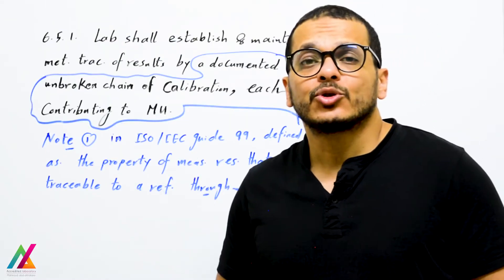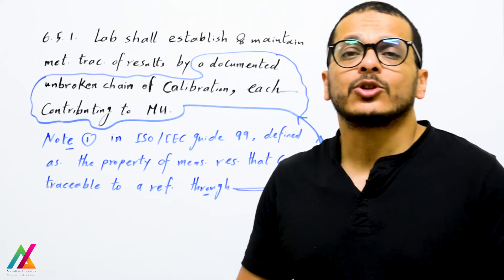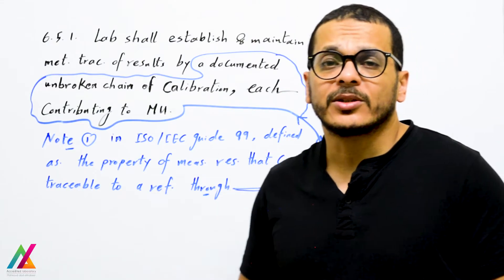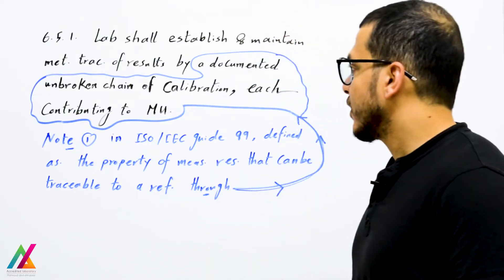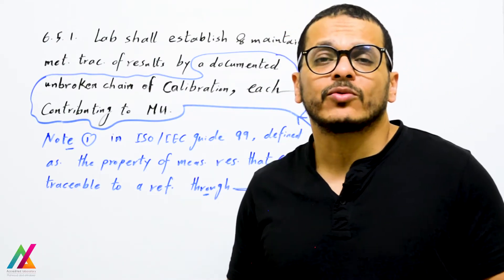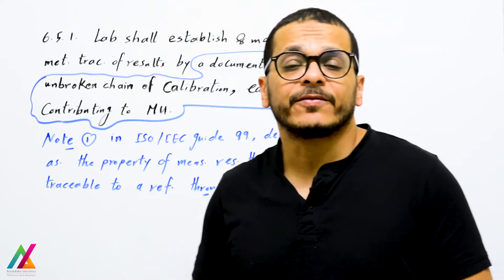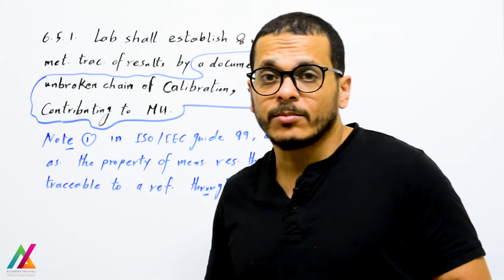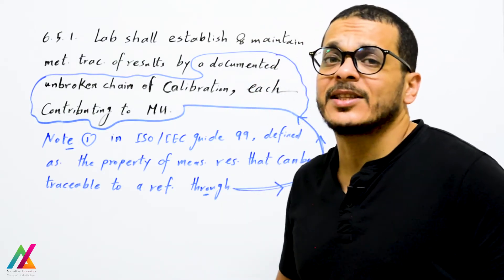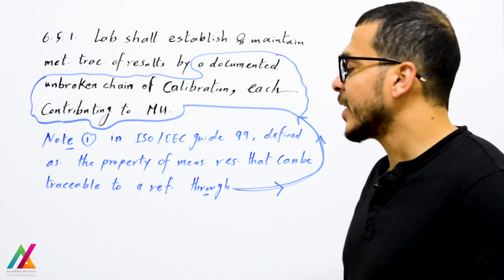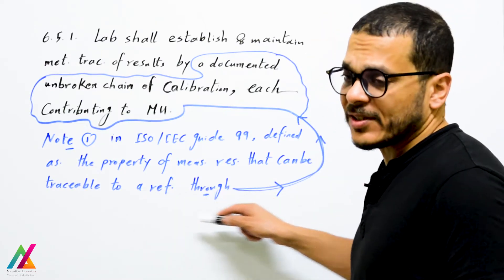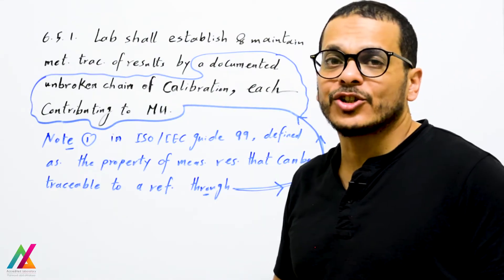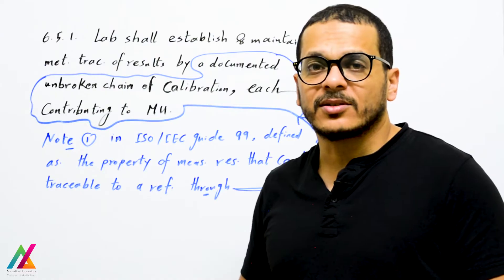The lab shall establish and maintain metrological traceability of results by a documented unbroken chain of calibration, each contributing to measurement uncertainty. This aligns with the definition in ISO/IEC Guide 99, which refers to the International Vocabulary of Metrology (VIM), defining metrological traceability as the property of a measurement result that can be traced to a reference through a documented unbroken chain of calibration, each contributing to measurement uncertainty.